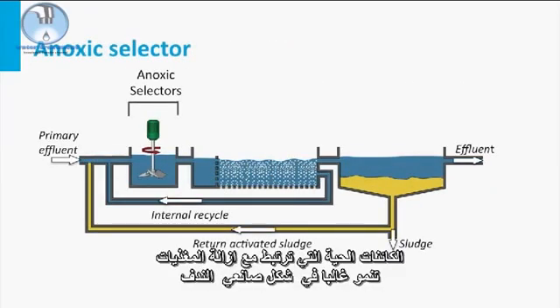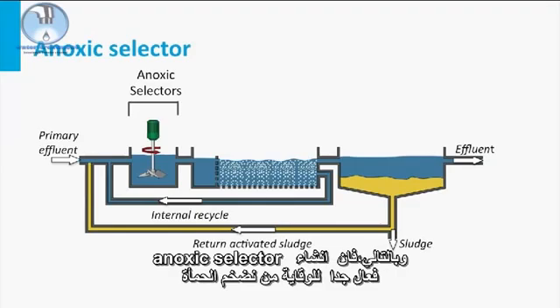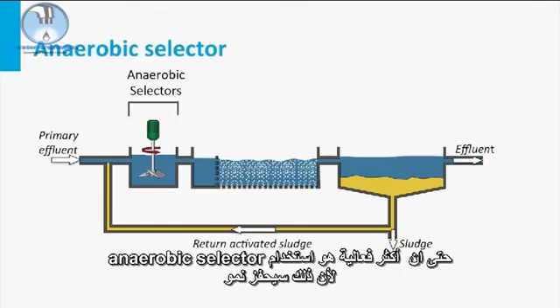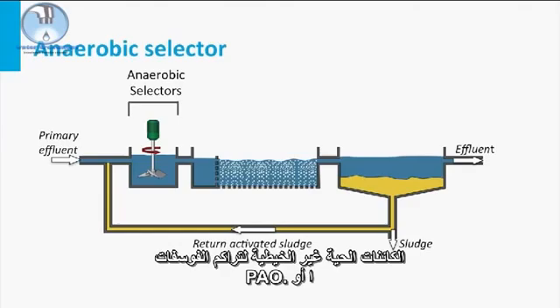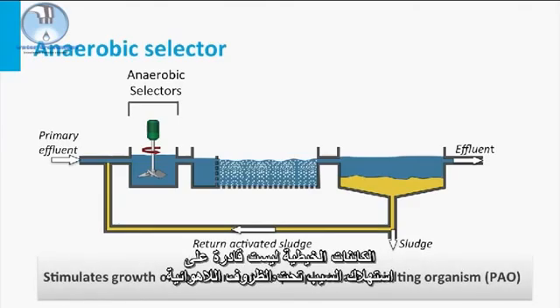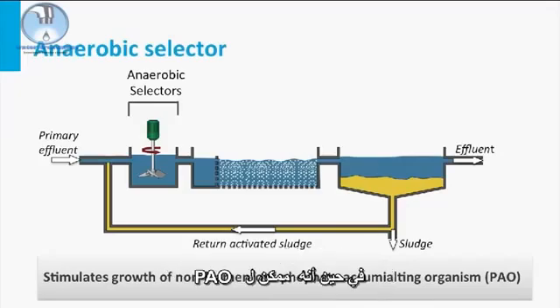Organisms that are associated with nutrient removal will often grow as floc formers. Therefore, introducing anoxic selectors is also very effective as a prevention of bulking sludge. Even more effective is the use of an anaerobic selector, since that will stimulate the growth of non-filamentous phosphate-accumulating organisms, or PAO. The filamentous organisms are not able to consume substrate under anaerobic circumstances, while the PAO can.